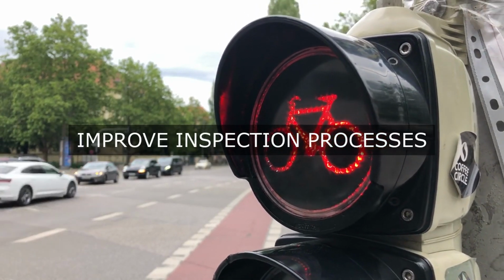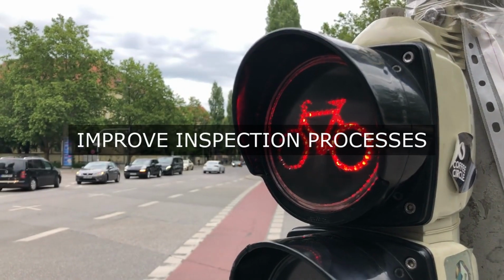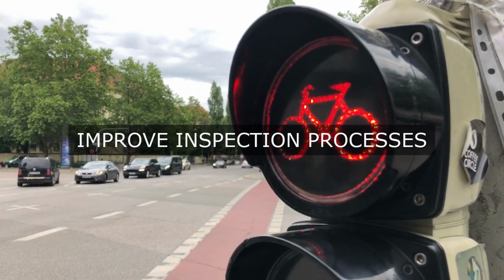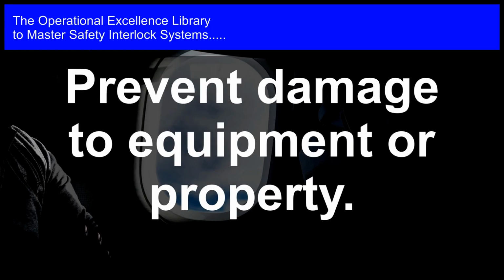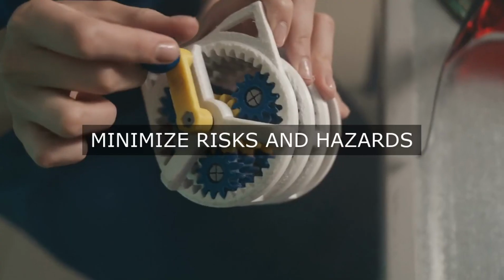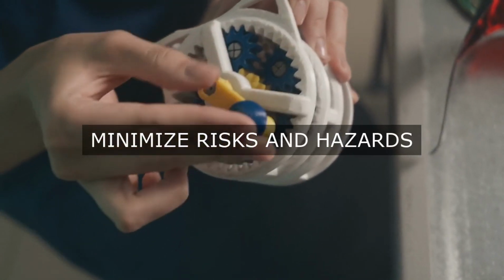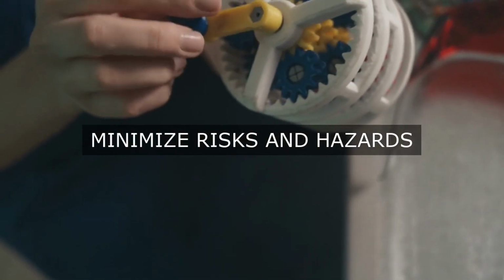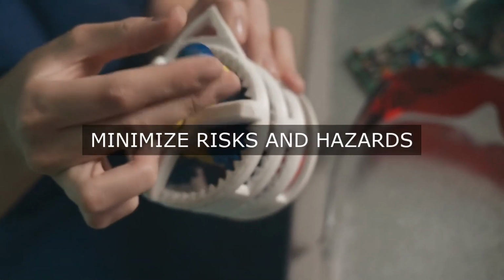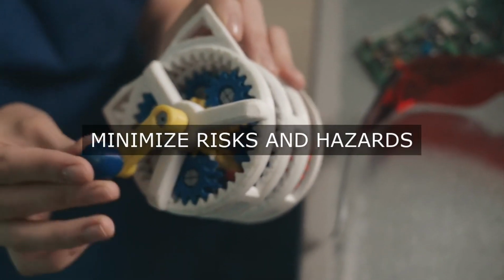Secondly, a SIS should ensure that equipment is operated within predefined safety parameters. This can be achieved through the use of sensors and safety-rated controls that monitor the equipment's operating conditions and prevent operation outside of the safe operating range. For instance, a temperature sensor may prevent a furnace from operating if the temperature exceeds a predetermined level, thereby preventing a catastrophic failure.